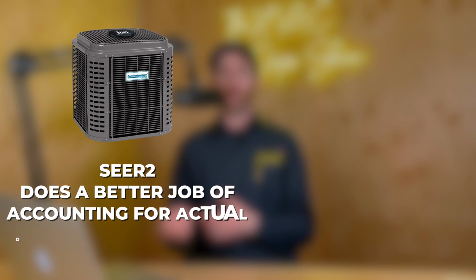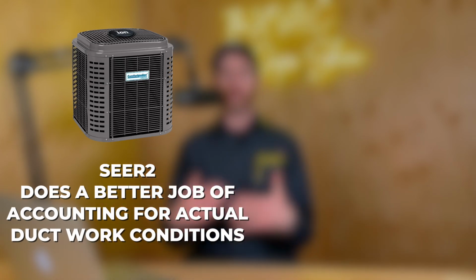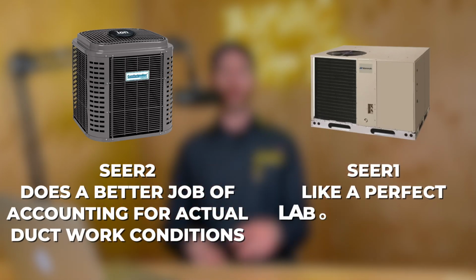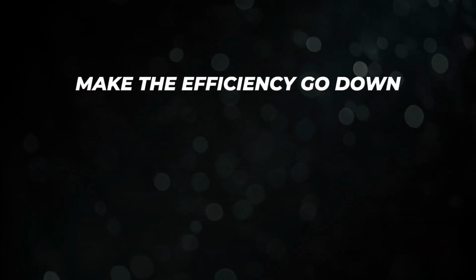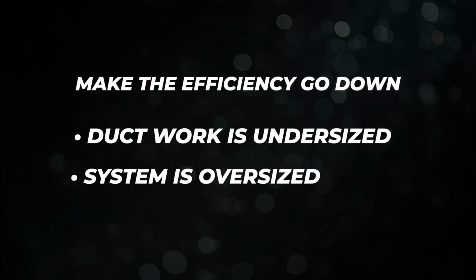One of the biggest changes is that SEER 2 does a better job of accounting for actual ductwork conditions we see in the field, whereas SEER 1 was more of a perfect laboratory study of efficiency. The stuff we run into in the field can make the efficiency go down, especially if the ductwork is undersized or the system's oversized for the home. If it's oversized for the home, that was a mistake made on the install, and the only fix is the right size system. But if it's oversized for the ductwork yet right for the home, you just need to modify the ductwork to allow for more airflow.